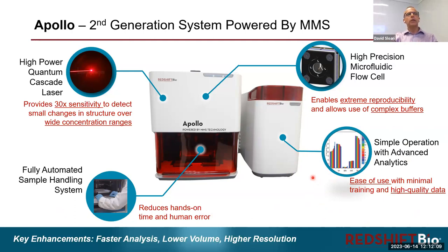The last key component is a microfluidic flow cell. One of the challenges with IR spectroscopy is very strong water absorption in the amide-1 band, which is where most people look for protein secondary structure. Our microfluidic flow cell allows real-time buffer subtraction — real-time background referencing — so we can subtract out the water signal as well as any signals from formulation buffers, complex excipients, or additives. This lets you look at your samples under the conditions you care about: in formulation buffer, at formulation concentration, under conditions where they'll be most stable.